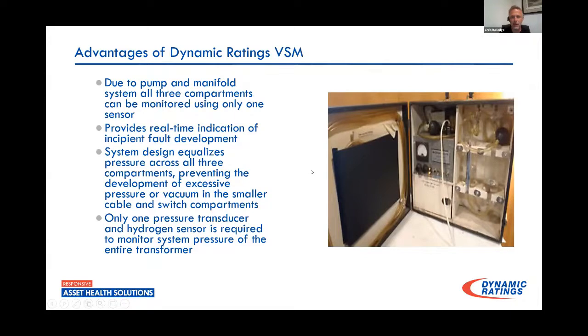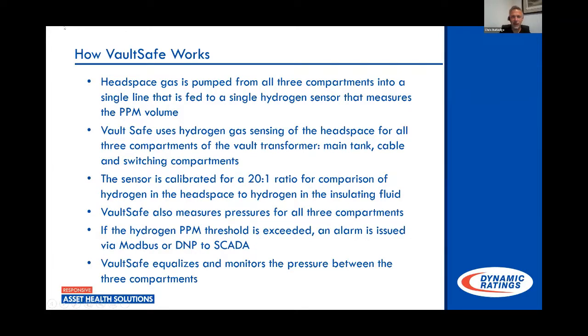And I just wanted to go over that because I wanted you to understand where I'm going with the monitoring, because I had gotten so used to that test and I had seen the effectiveness of it. And I thought, well, why don't we apply this to an online type process? That way the transformer is being looked at 24 hours a day rather than once every 5 to 8 years when we can get around and get the whole system checked. So the VaultSafe monitor is actually a manifolded system that allows all these headspaces to be tied together. You can't mix the oils from these compartments, and that's in the IEEE. If you go and look at your IEEE, I believe it's C57.12.